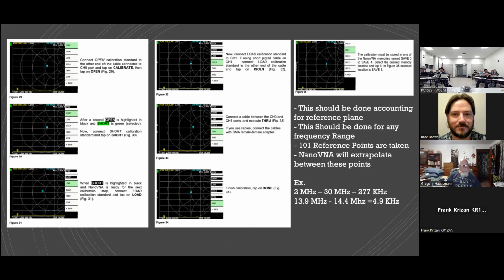And then the through will be a connection where you connect the cable from one port to the other. You have to do open, short, and load for any calculation you're doing. So if you're just doing SWR, that's all you need to do. But if you're going to test something like a filter or anything that requires 2 ports to be connected in and through, you'll need to do the configurations for the isolation and the through. Make sense?